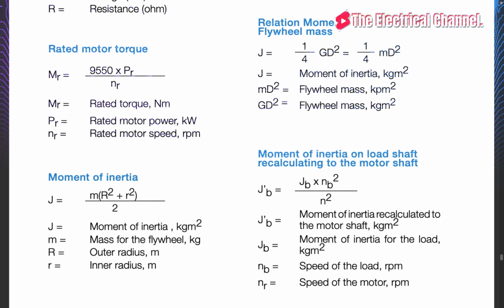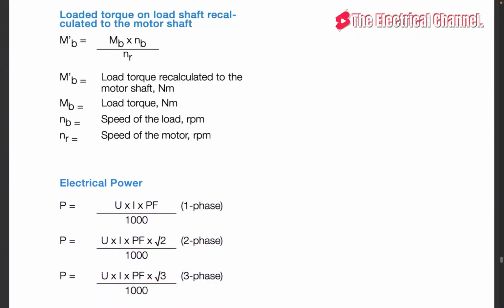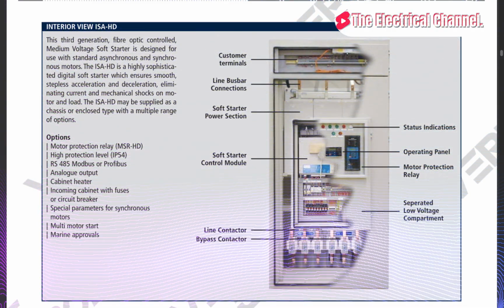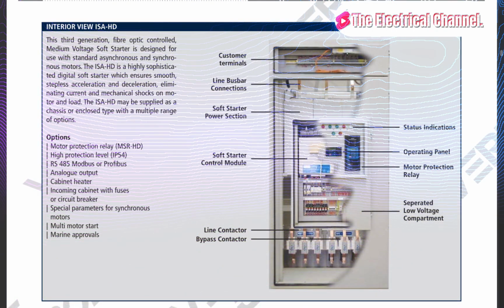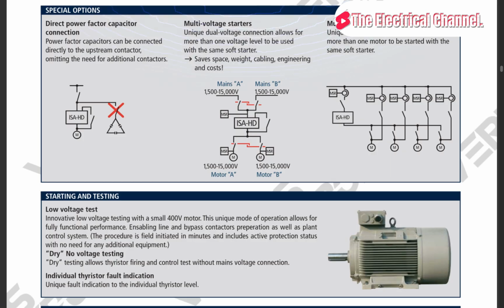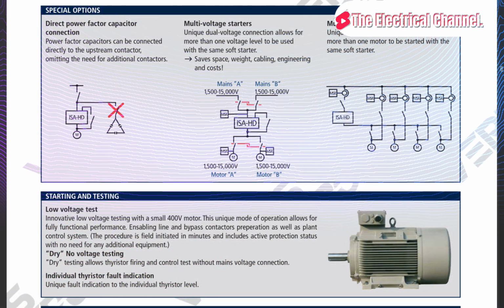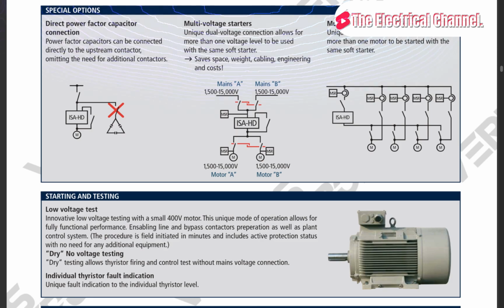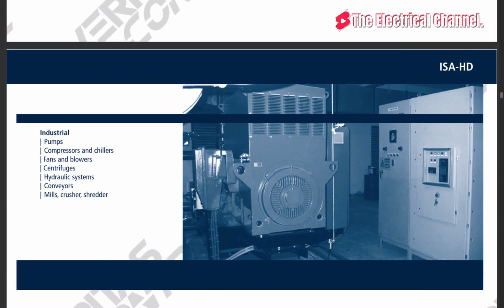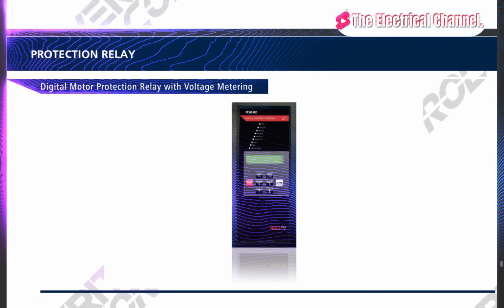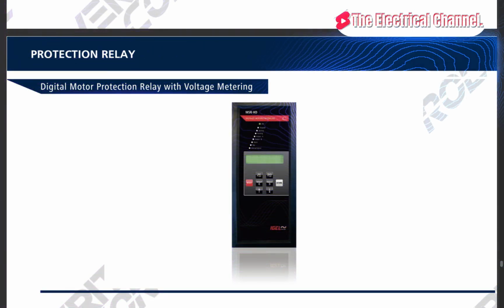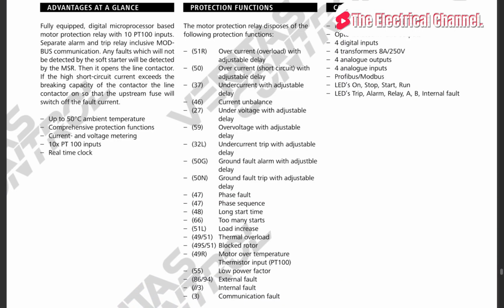Torque control is a function that will control the torque of the motor instead of the voltage. This is especially useful when stopping pumps in order to avoid water hammering. On soft starters with torque control, it is possible to select between a torque ramp or a voltage ramp, both during start and stop. These parameters are called start mode and stop mode.